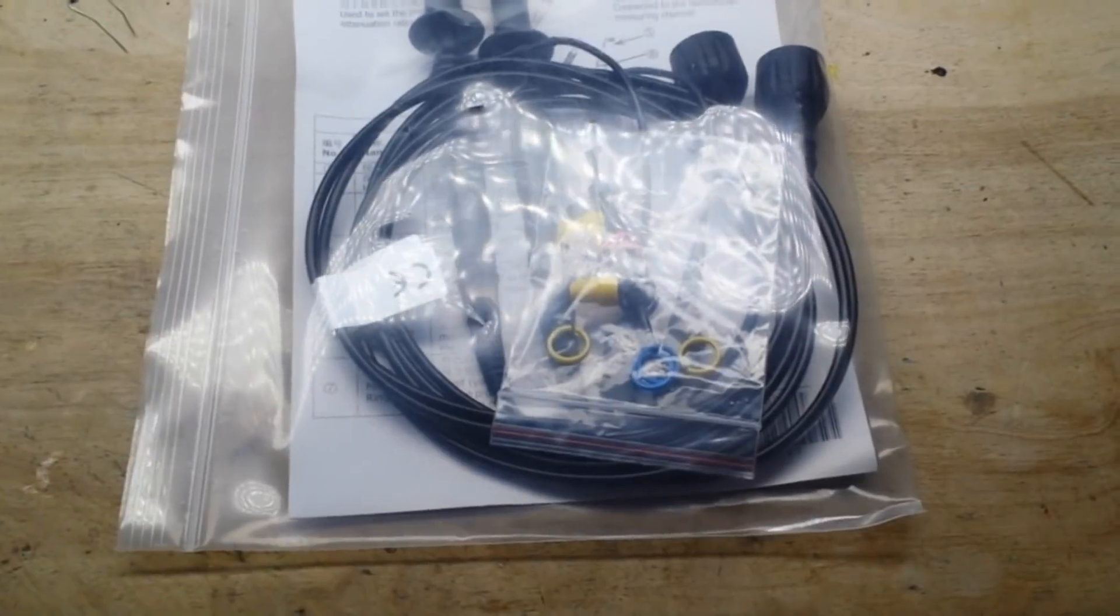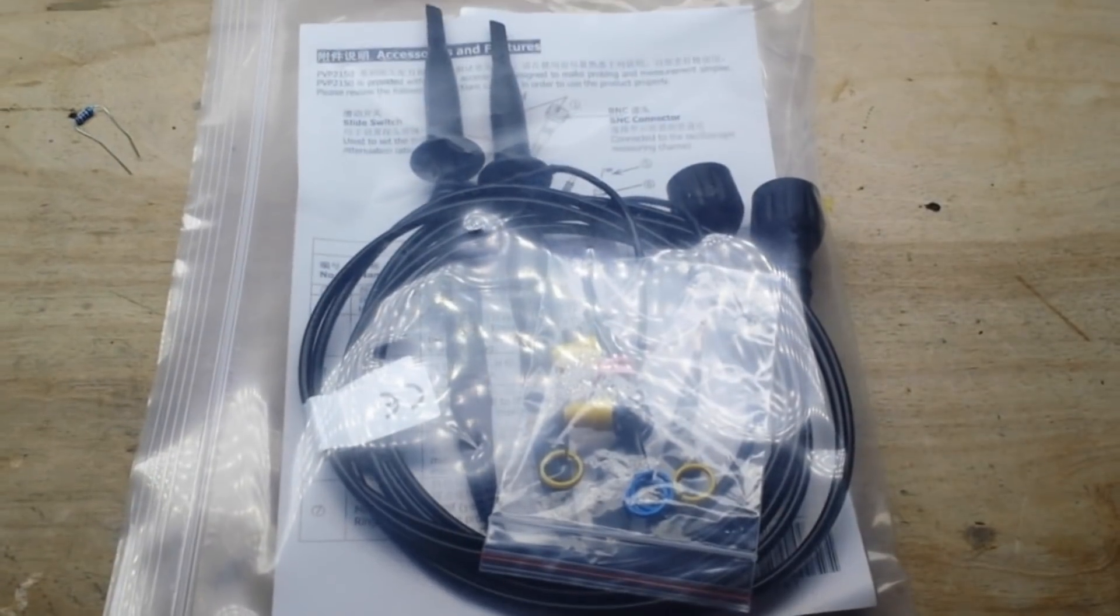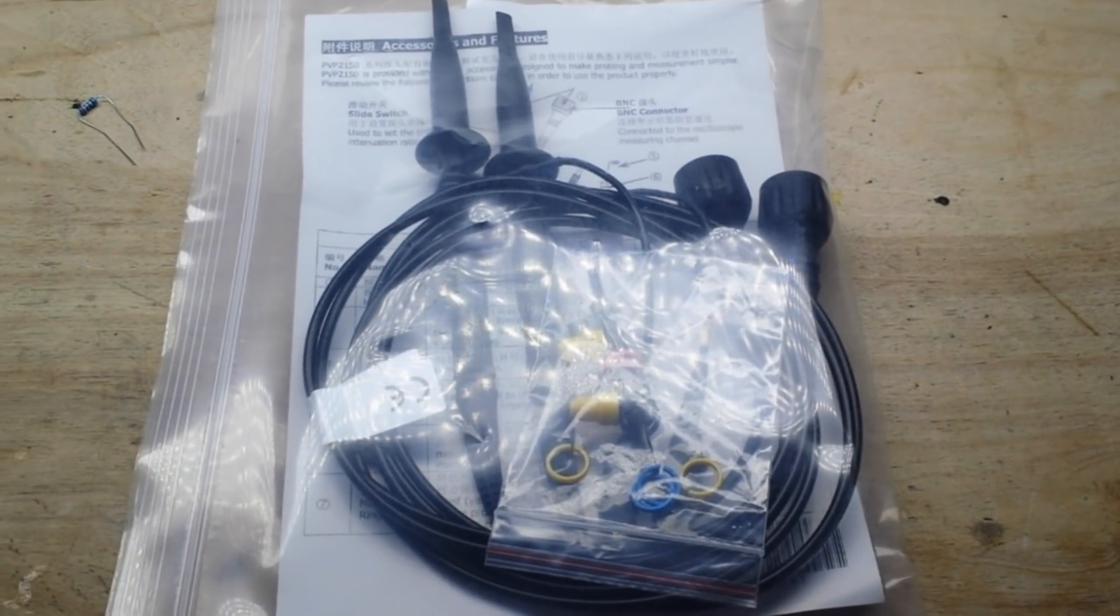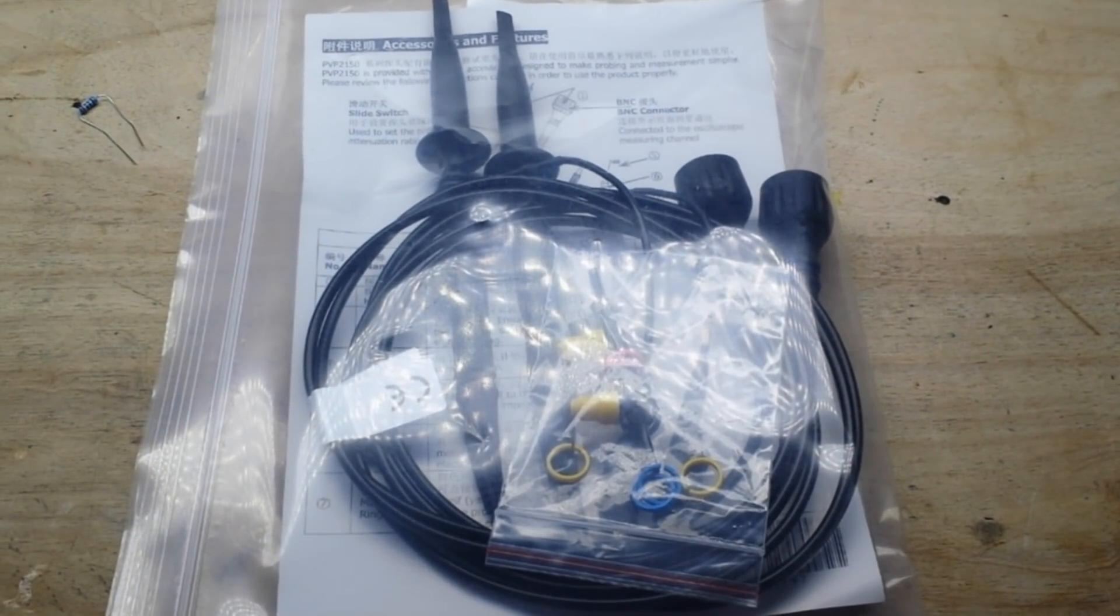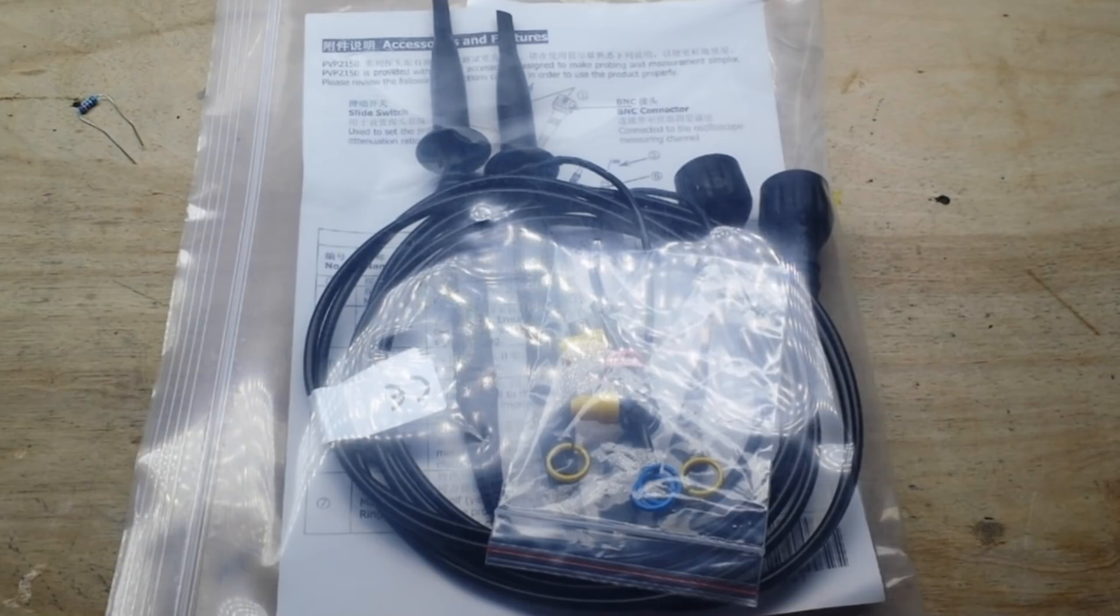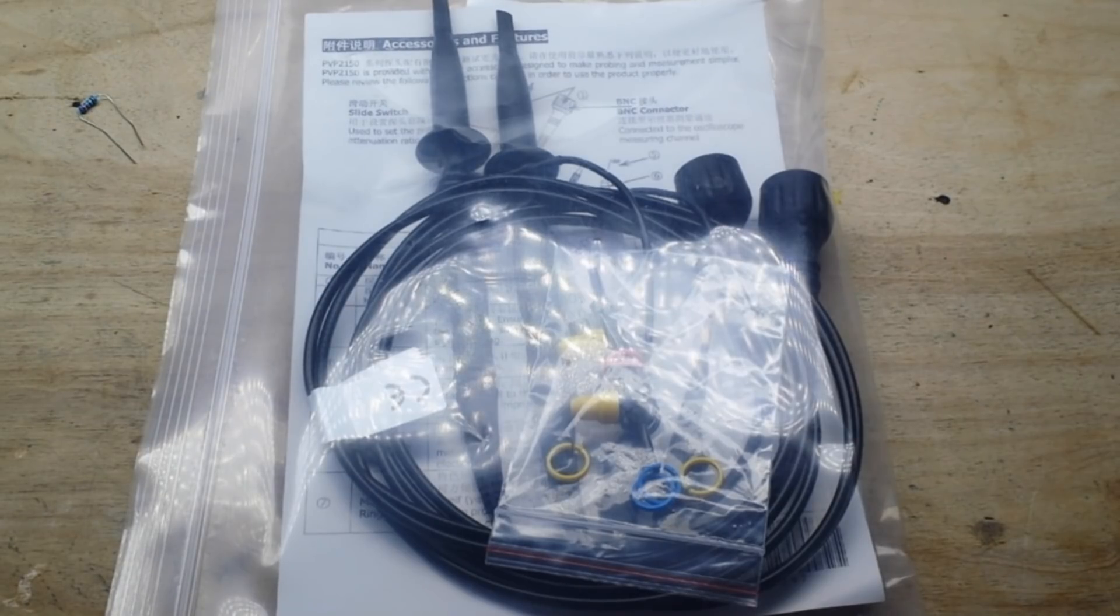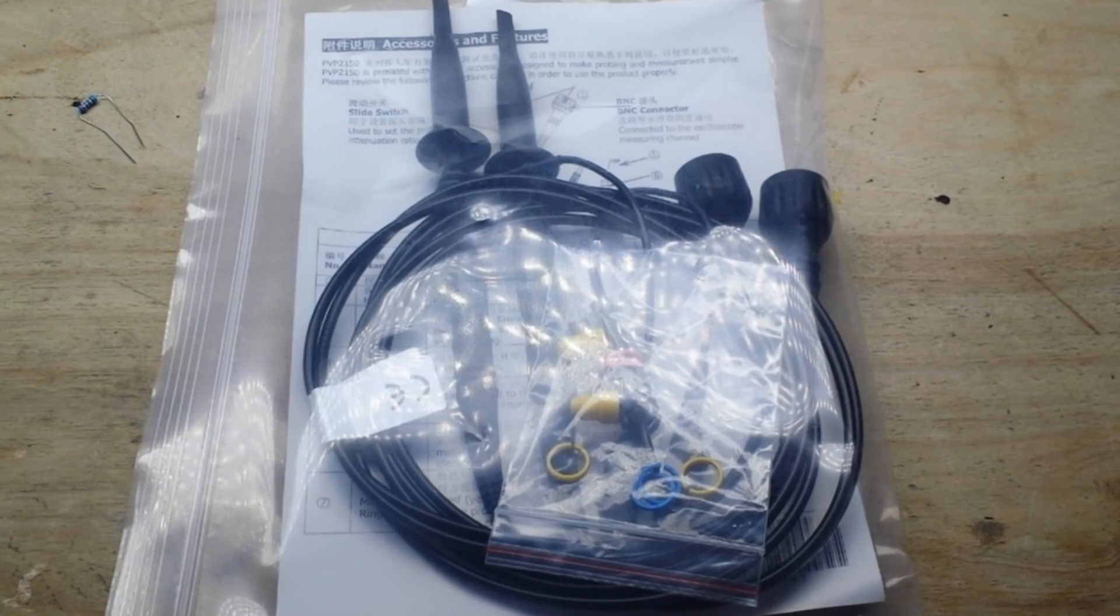Okay, self calibration is done. You either had to restart the scope or not depending on the model of scope. It really doesn't matter. The next thing we need to do is take a look at our probes and compensate them. Let me show you what I mean by compensating the probes. They are more than just a wire with a probe at the end.